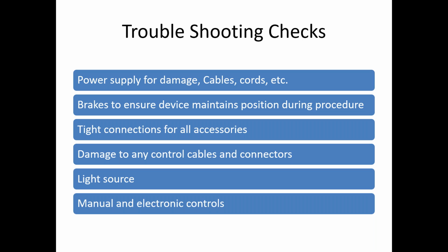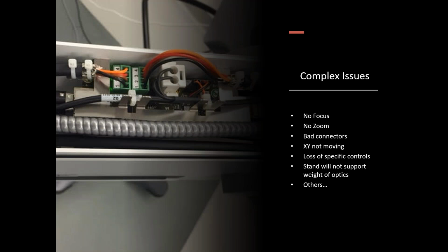So there are light source issues, manual and electronic control issues, and some more complex issues we've run across like no focus or no zoom. Depending on the microscope, those could be zoom and focus motor issues, or they could be boards - OPMI boards, OPMI control boards, or bad connections.